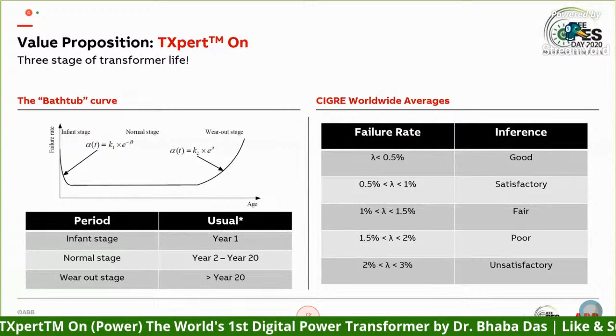So what we did, we used that 1% to do some calculations. Within that 1% failure rate, with your existing protection devices, you can save around 30% of those, whereas 70% is not detectable. And within that 70%, 10% will result in catastrophic failure, like fire, whereas 90% are non-catastrophic.